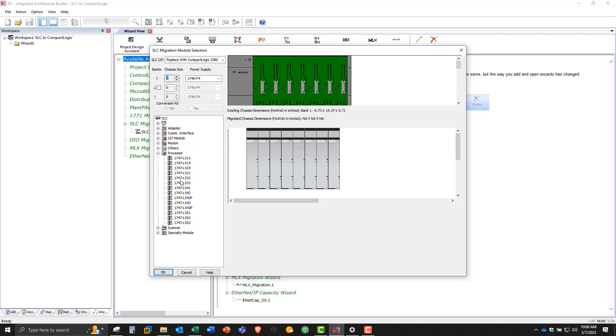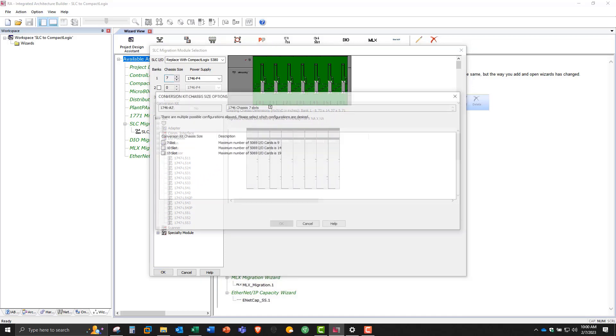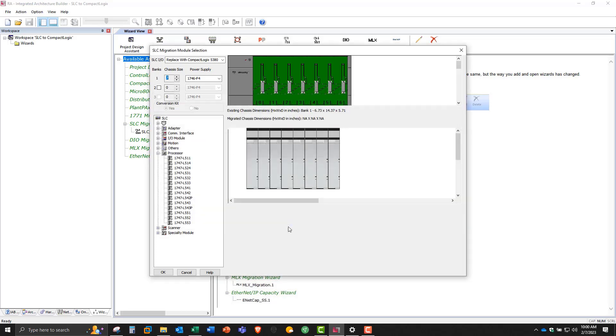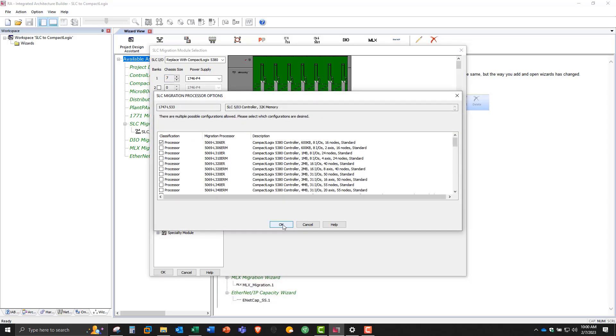So the first thing we'll do is pick our processor for the SLC. We'll pick this L533 module. This is a SLC 503, so I'm going to hold down with my left mouse key and drag it up to slot 0. Now we're being asked what conversion kit chassis size we should use. I'm going to pick 7-slot. For the processor, I'm going to pick the L310ER to give me a little more memory to work with, and it supports 8 local I/O cards.